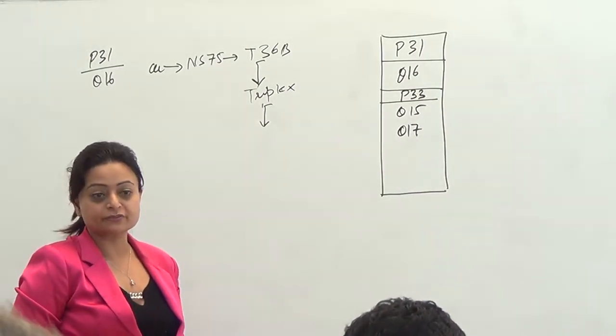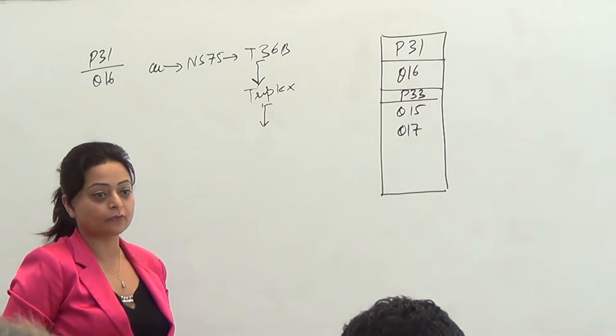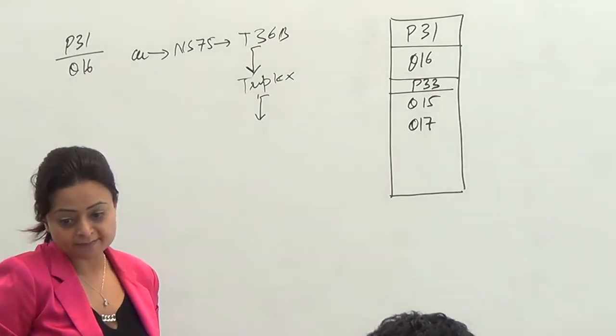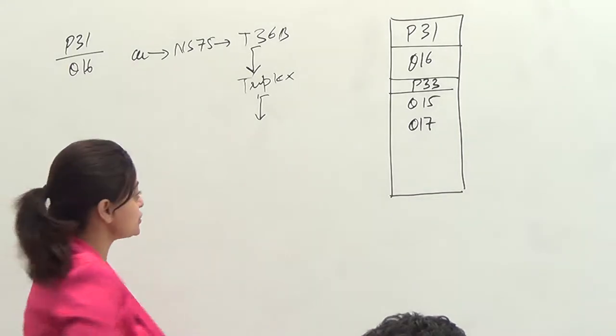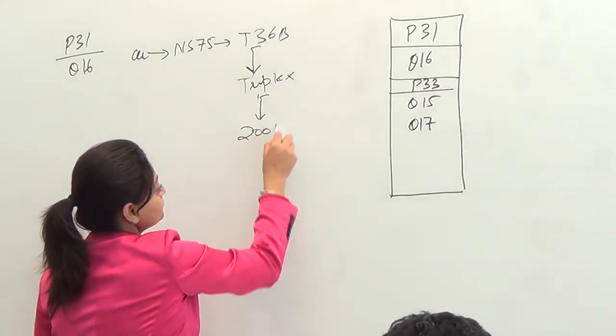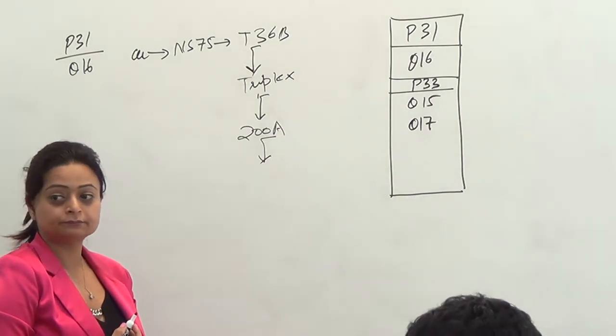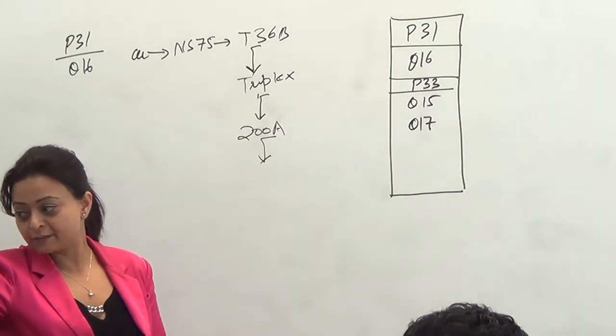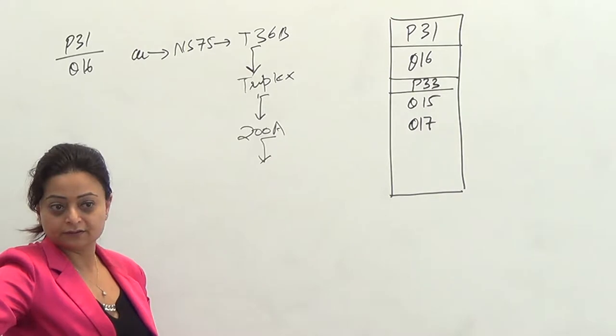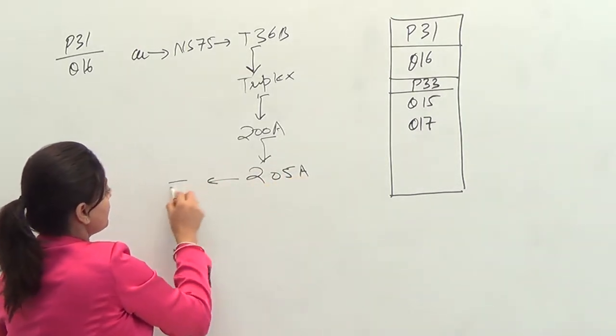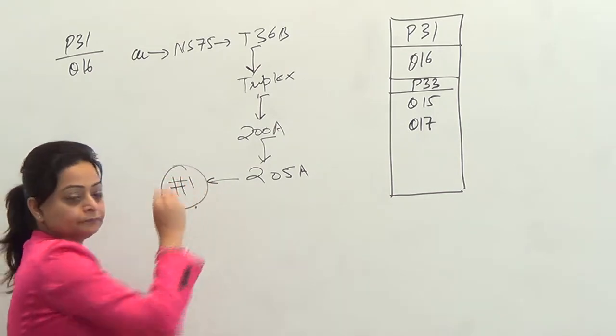He didn't say in the question 120 volt single-phase system. 120/240 is two phases, one neutral, which is what? A triplex. So, ampacity is 200 amps given. Under 200 amps, what's my closest match? Which is referring to how many amps? 205. That refers to? Number one. Good job. Done.